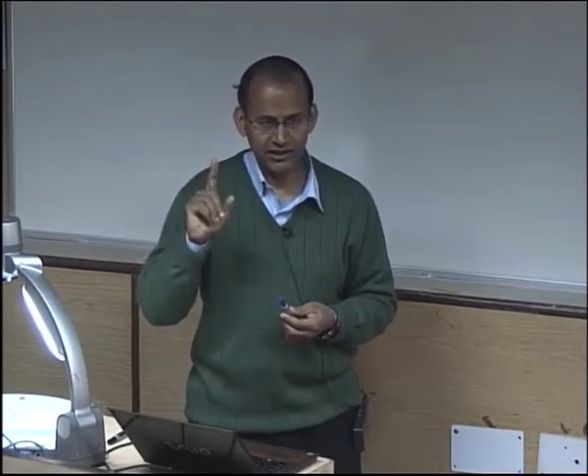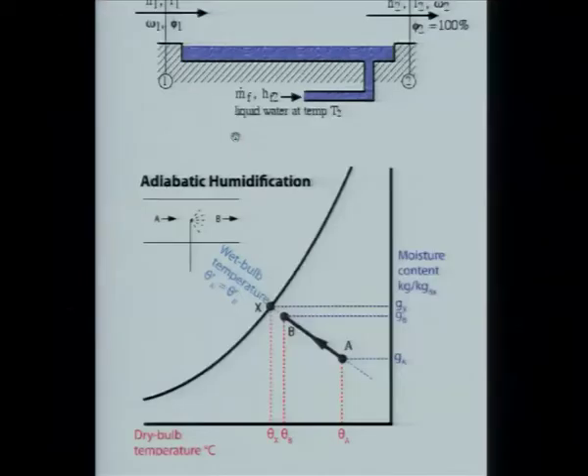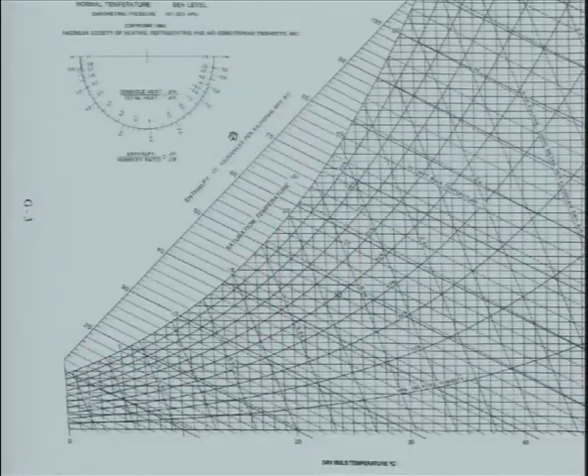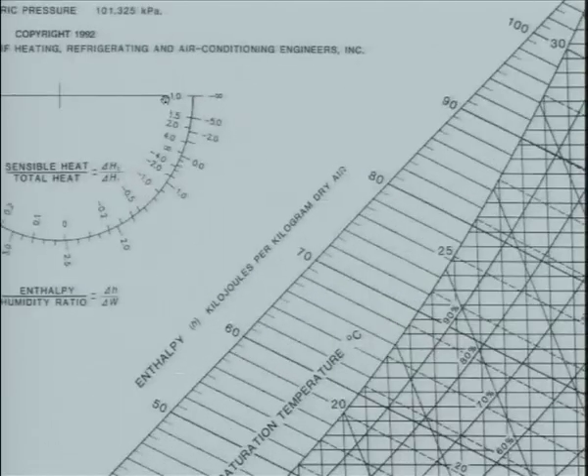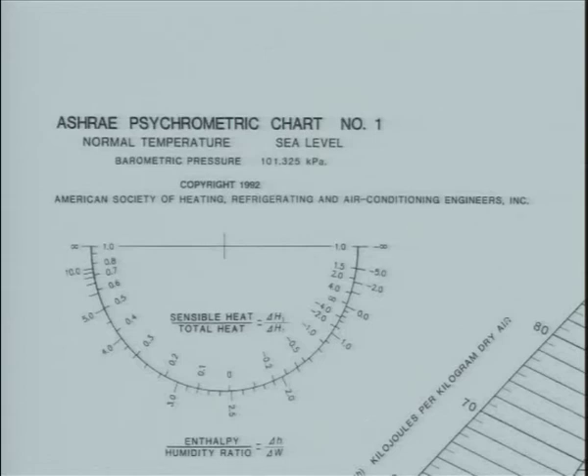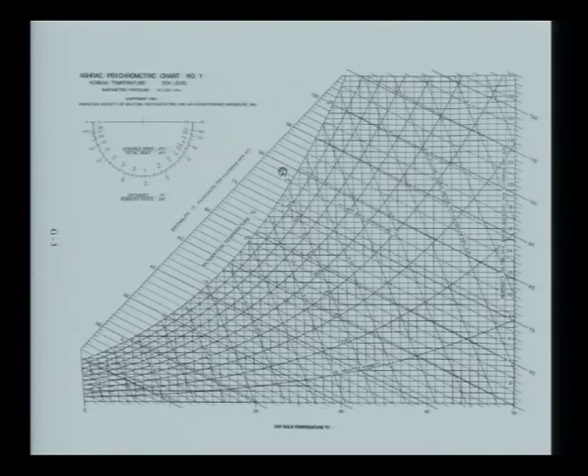One important note: the psychrometric chart is plotted for one particular pressure, normally stated at the top. For this chart it is sea level — 101.325 kPa — covering 0 to 50°C. If the pressure is different, you need either a different psychrometric chart or must calculate from the fundamental formulas. That concludes the introduction to the psychrometric chart; we will now take questions.